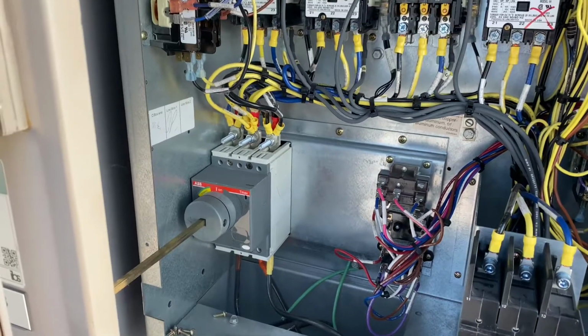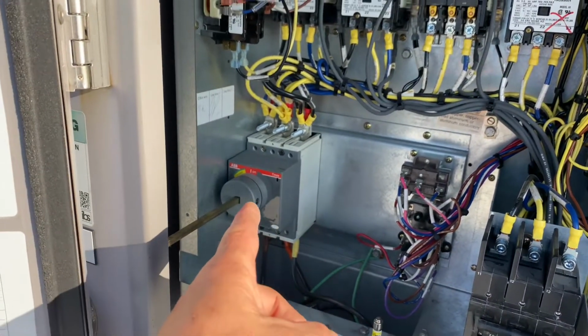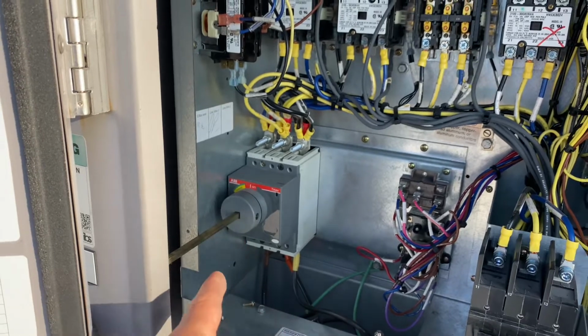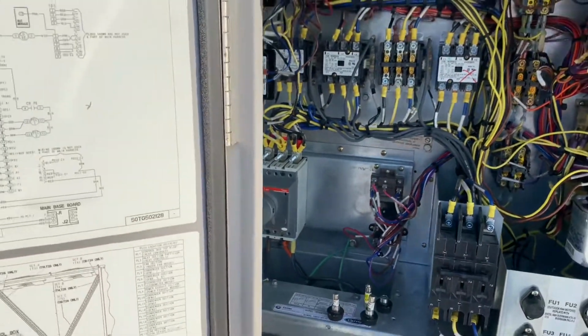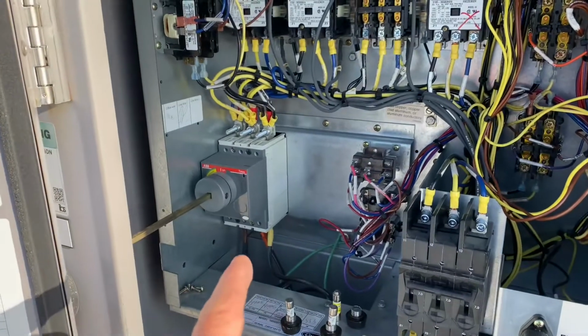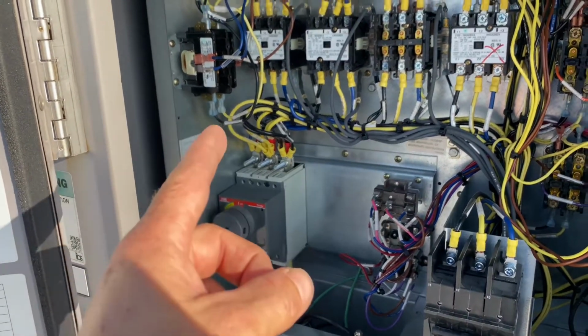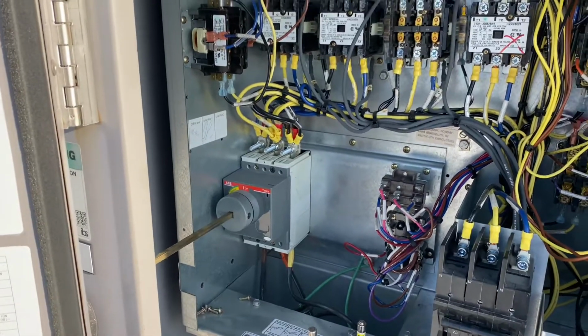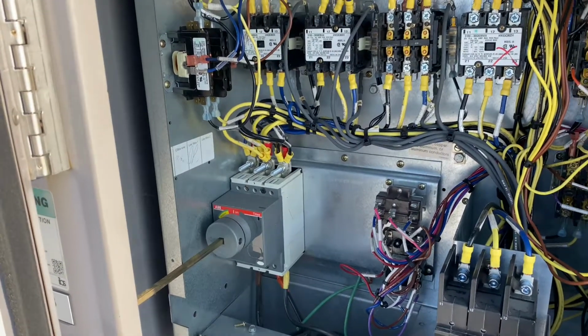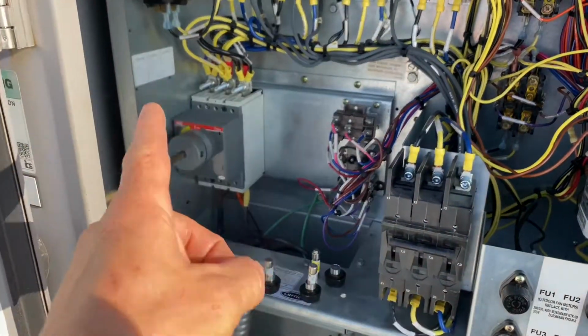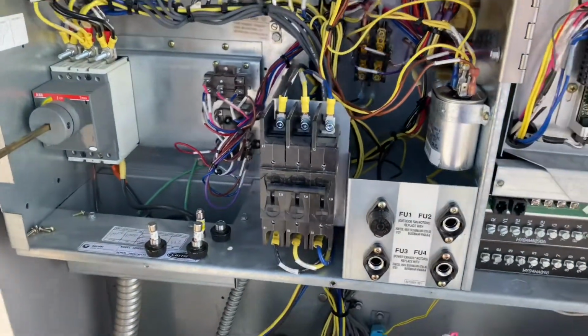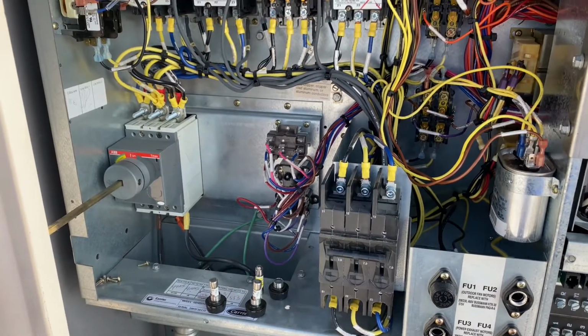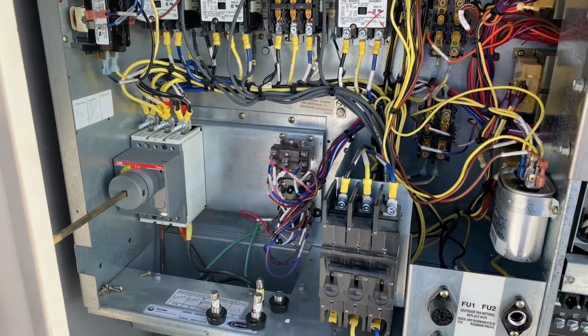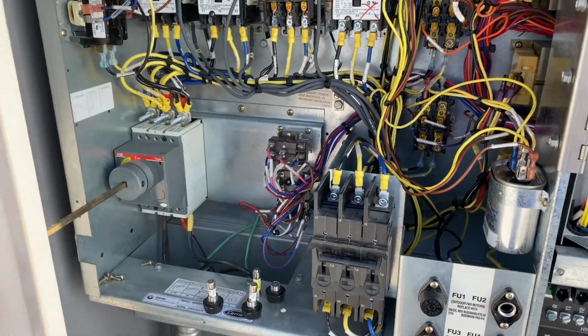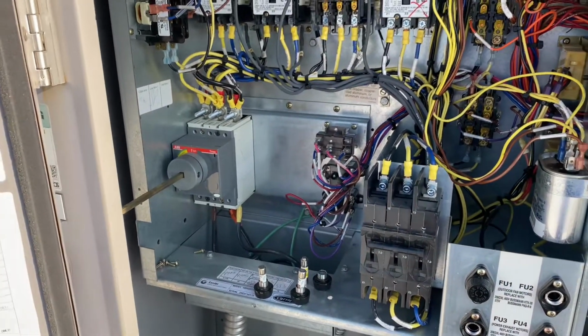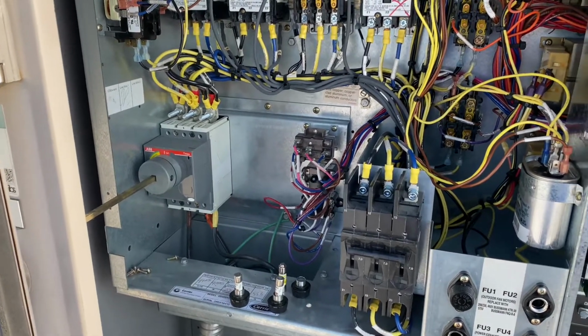Off your main points, you want to hit them first. Obviously your main disconnect, make sure it's getting full power, which in this case was 480 volt phase to phase, on load side and line side, getting 480 volt phase to phase and 280 to ground, each phase to ground, both on that disconnect and this circuit breaker. So I knew I had power, the right amount of power coming in, as far as I haven't dropped a leg or whatnot. There's no main fuses coming into this as far as a fuse disconnect, just circuit breakers.